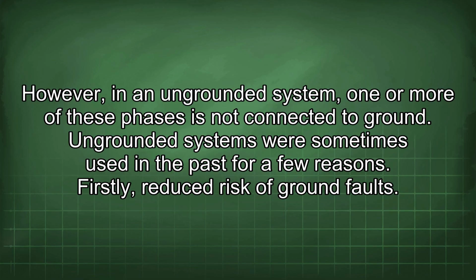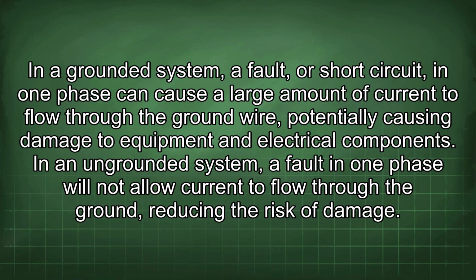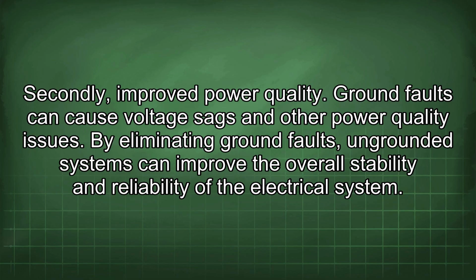Ungrounded systems were sometimes used in the past for a few reasons. Firstly, reduced risk of ground faults. In a grounded system, a fault, or short circuit, in one phase can cause a large amount of current to flow through the ground wire, potentially causing damage to equipment and electrical components. In an ungrounded system, a fault in one phase will not allow current to flow through the ground, reducing the risk of damage. Secondly, improved power quality.